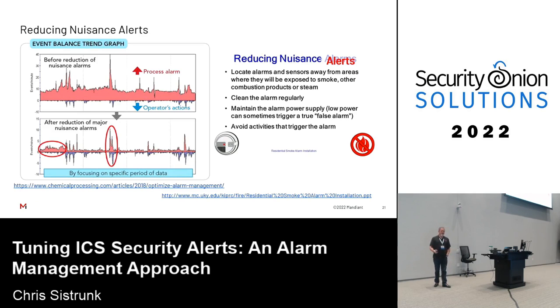So how do we reduce nuisance alarms and reduce nuisance control system security alerts? Just the same way we try to reduce them with security onion tuning. Here's an example from this blog post from chemicalprocessing.com. They had a reduction of nuisance alarms. They have the process alarms, which is up in red, and the operator's actions, which is blue below. Once they reduce the nuisance alerts, you can see the signal to noise ratio changed significantly, and the operator can see when they need to act upon which alarms are happening. Same way if you have too many cybersecurity alarms coming in, right?